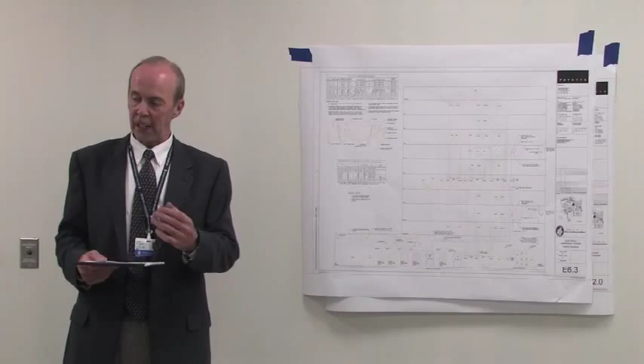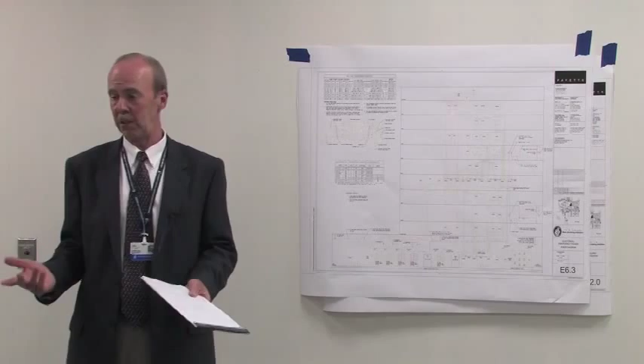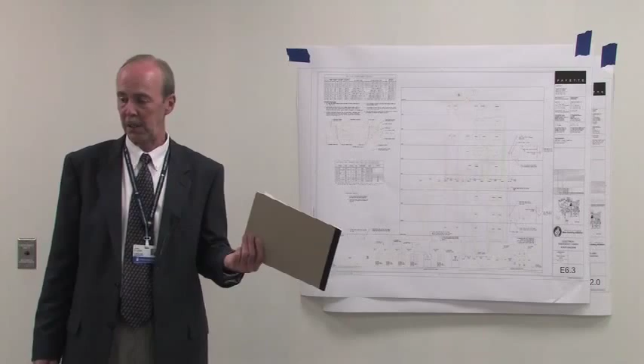Our design loads tend to be a little fatter than the actual demand loads, because as engineers we can only use certain demand factors. I can't use actual demand factors, and we all know those demand factors that utility companies actually see are much lower. So my load reading says we're going to have 1,600 to 1,700 kVA in this building. You're not going to see that. You will not see it. But those are the demand factors I can take.